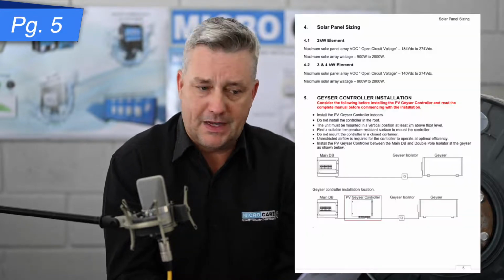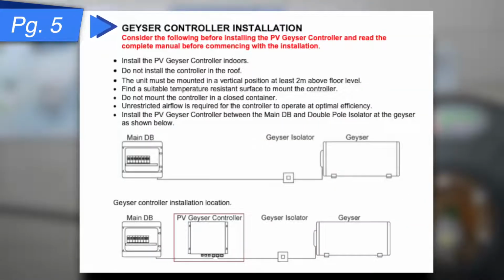And then on to number 5, you'll see the geyser controller installation. A couple of guidelines for you there. Please install it indoors. Do not install it in the roof, merely for the reason that if the end user needs to get to the controller to switch it off in an emergency case, maybe something has happened on the roof, then they're going to have to climb in the roof to do that, whereas if it's available within the house, it's much easier to resolve the situation. It must be mounted in a vertical position. We recommend 2 meters off the floor, sort of eye level, so that you can have good interaction with it.